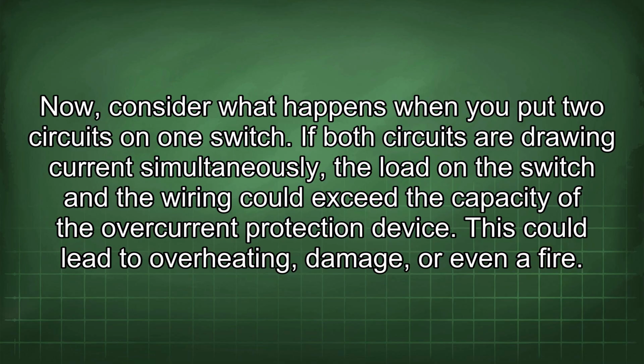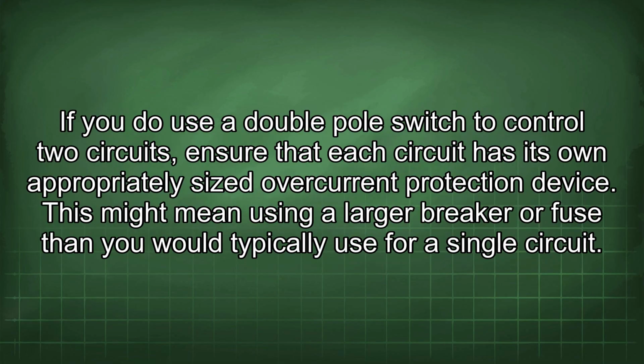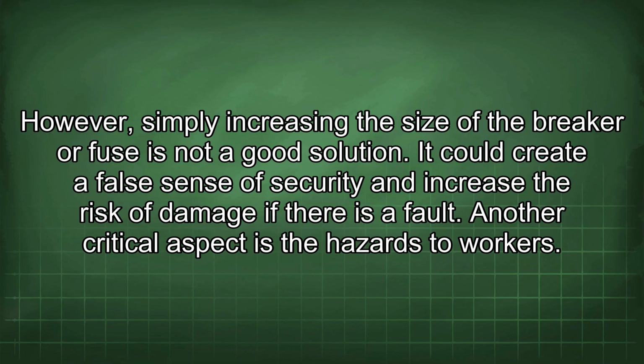If both circuits are drawing current simultaneously, the load in the switch and the wiring could exceed the capacity of the overcurrent protection device. This could lead to overheating, damage, or even a fire. If you do use a double-pole switch to control two circuits, ensure that each circuit has its own appropriately sized overcurrent protection device. This might mean using a larger breaker or fuse than you would typically use for a single circuit. However, simply increasing the size of the breaker or fuse is not a good solution. It could create a false sense of security and increase the risk of damage if there is a fault.